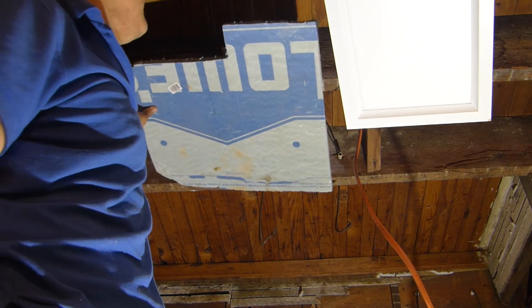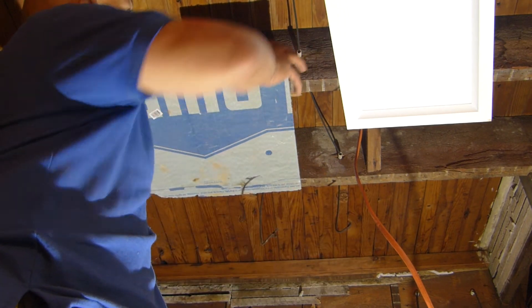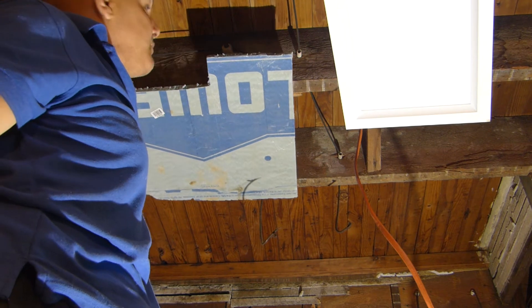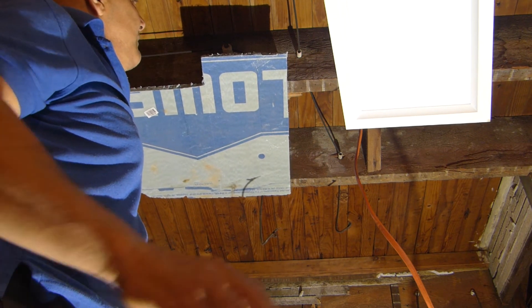Bridge it with some insulation like that, and then run your insulation on top. Your bay down below would be full, and then it comes up and you go over top of this rigid insulation with the same amount of insulation. This will allow you to have the compartment still open. It's not code that you do this, but the results I read from Pennsylvania's weatherization program show they really think it's ventilation-related that the wiring overheats. The fires were in the attic, and the only thing different was the weatherization — insulation added around the knob and tube, at the connectors.